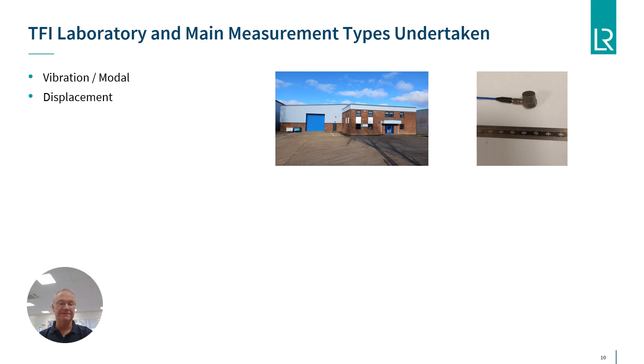Displacement measurements are usually undertaken to establish displacement variation relative to other structure or equipment. We usually use eddy current or laser sensors for measurements of rotating shafts to establish, amongst other things, radial vibration and to obtain orbits. For measurements involving non-rotating targets, contacting type sensors such as LVDTs can also be used.